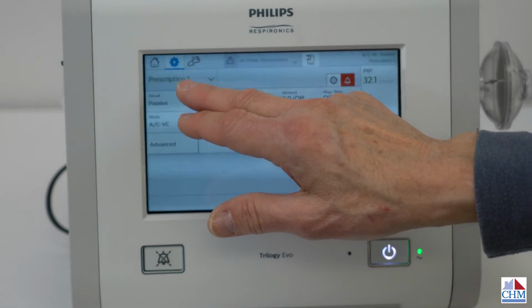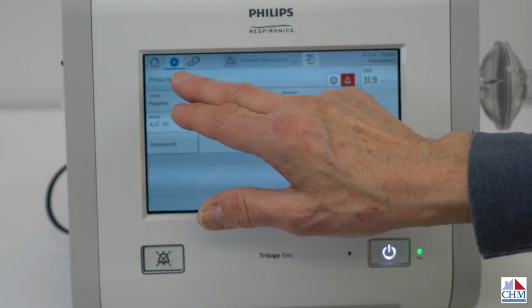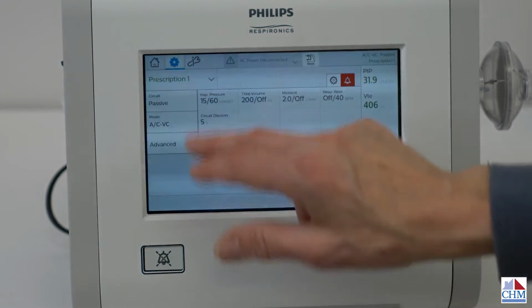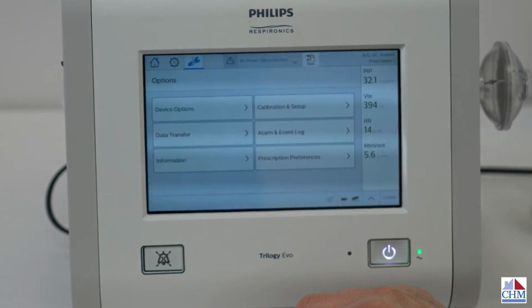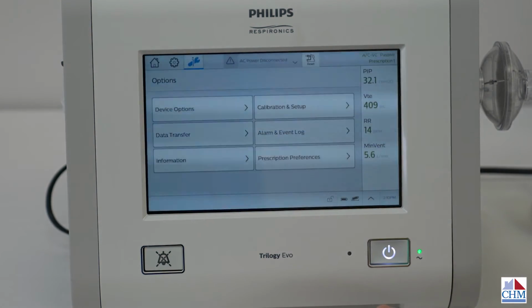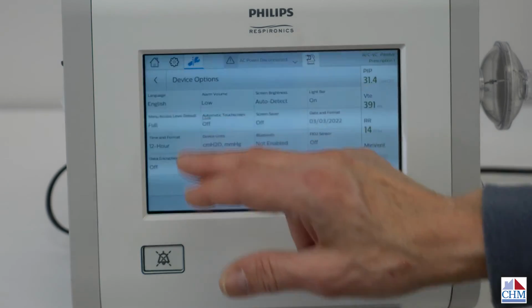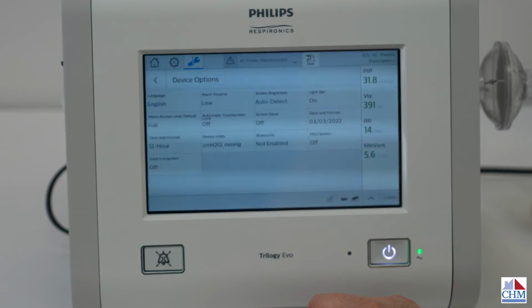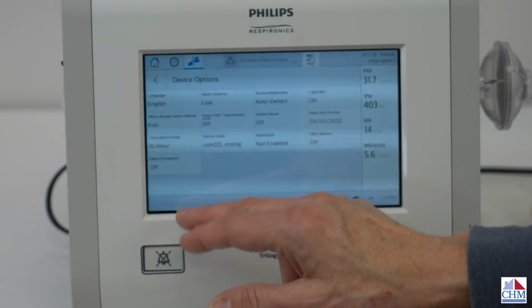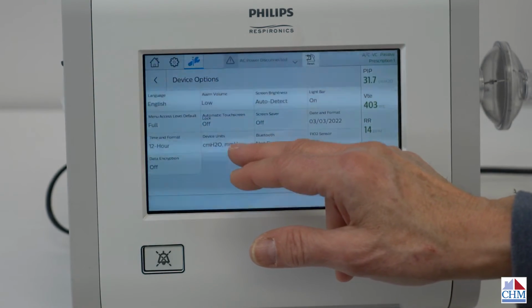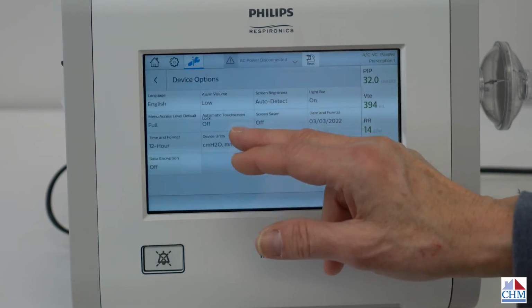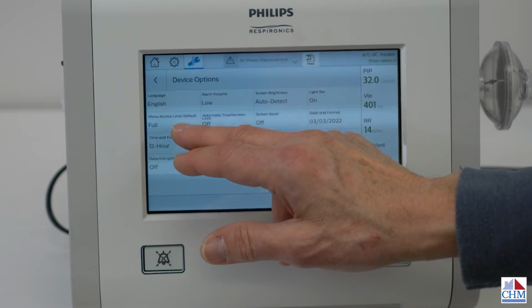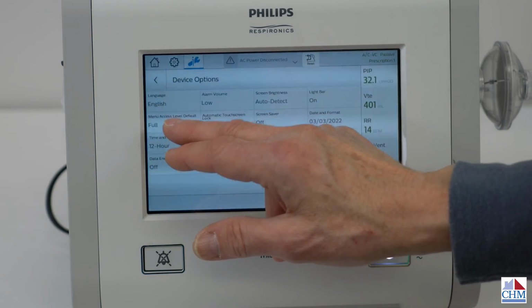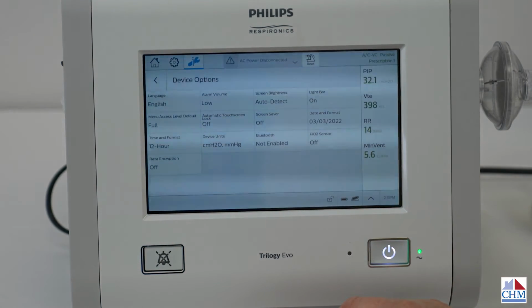And then, following along, if we want to keep going from home to going into the settings, if we hit the wrench, it'll take us into the options menu. And in the options menu, there's several things we can look at. For device options, we can look at the language, the volume of the alarm, and automatic touchscreen lock. We can change the menu level access to limited, which would mean that we need to unlock the ventilator in that case.